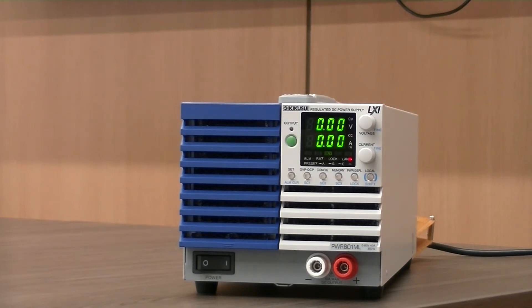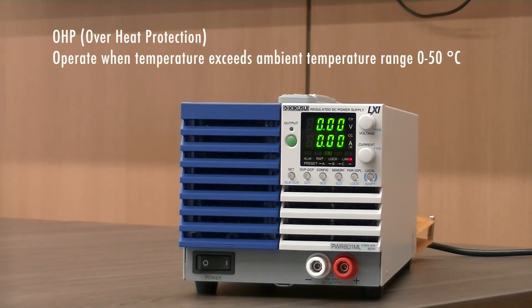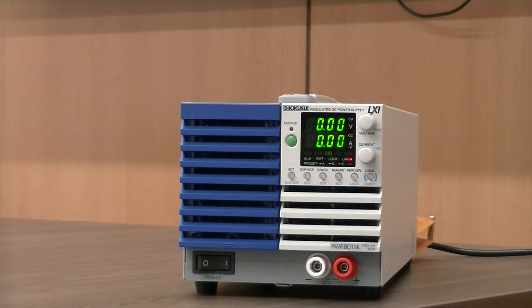This protection is activated when the PWR01's internal temperature rises to an abnormal level. This can be caused by a testing environment that exceeds the power supply's operating ambient temperature range, which is 0 to 50 degrees Celsius, when the air inlet or outlet port is blocked, or when a fan motor stops working.